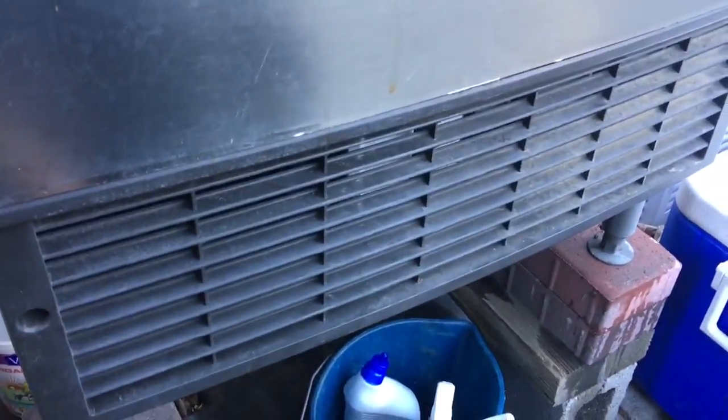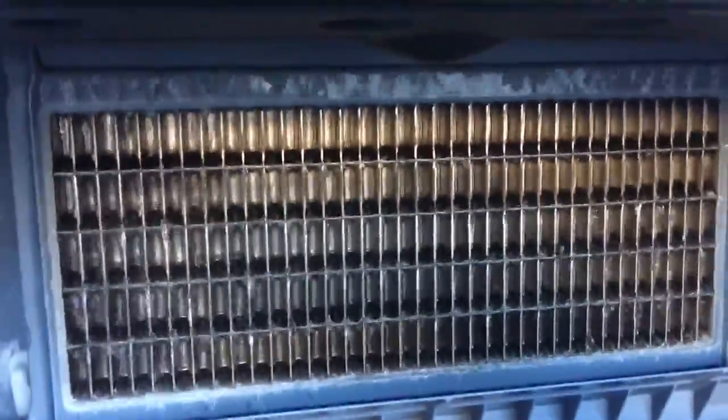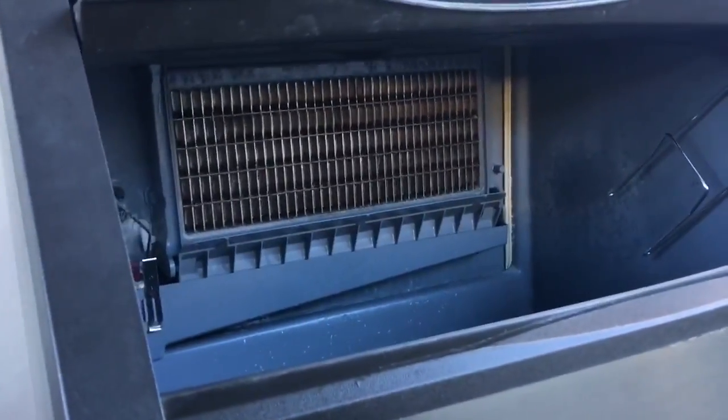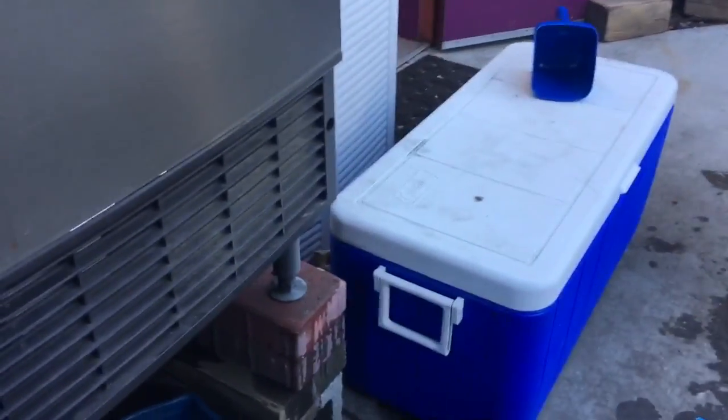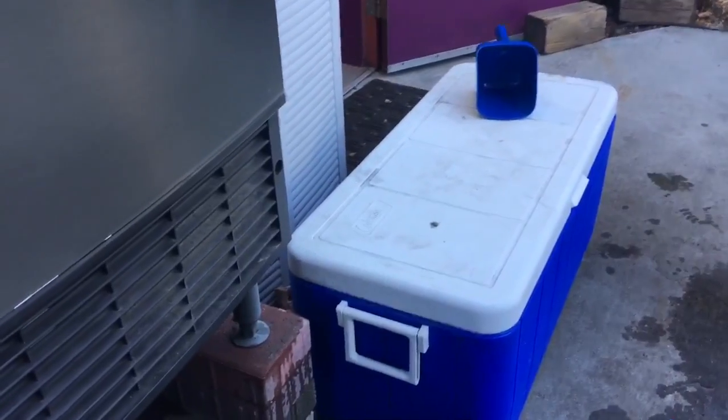It's about 75 out here today. The new fan cycle switch is working and we're making a uniform batch of ice — it's just starting. We'll watch it make a batch and drop here before we call this one good. Oh, and then I gotta shovel all the ice back to the bin — I brought my cooler from home. That's my cooler, it holds lots of beers. Or sometimes you can catch a fish and put some dead fish in there.